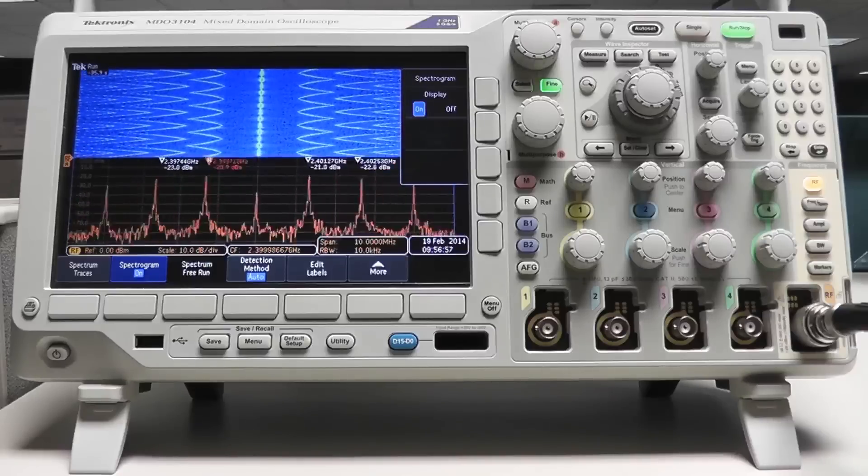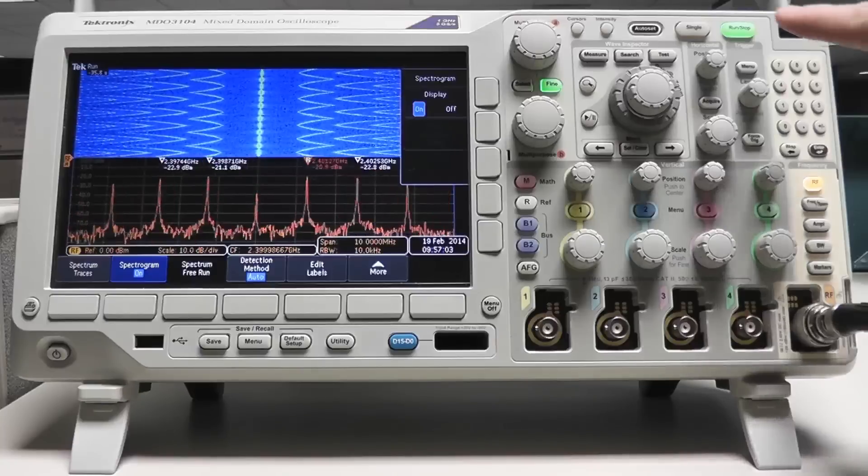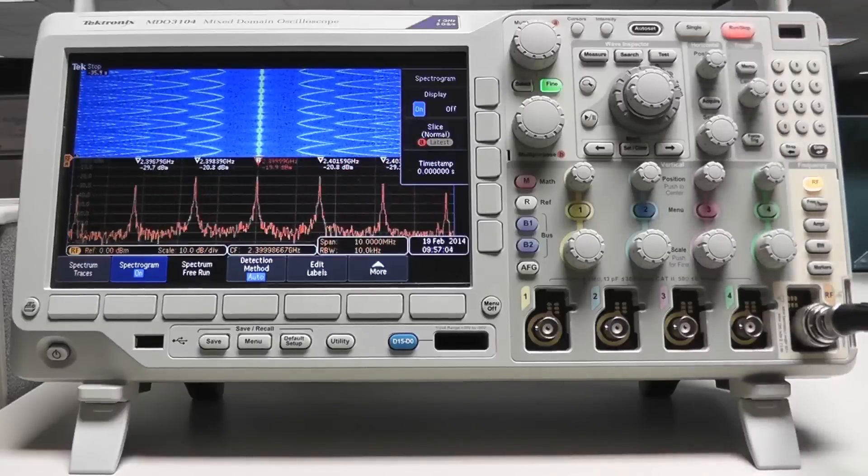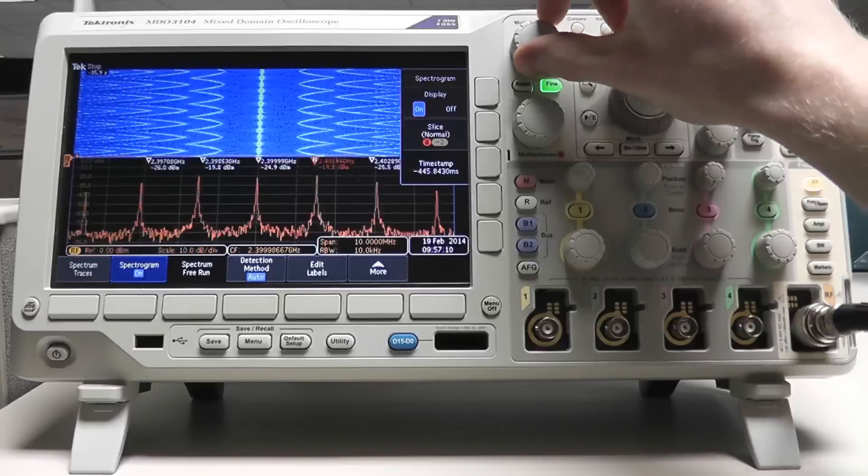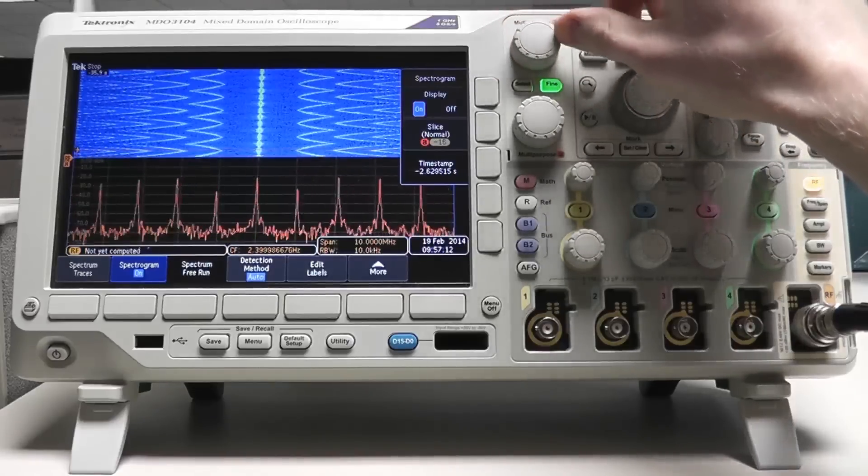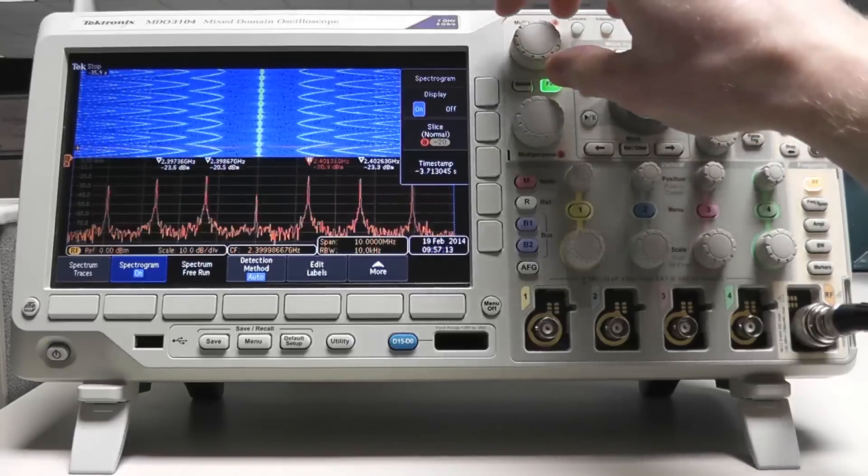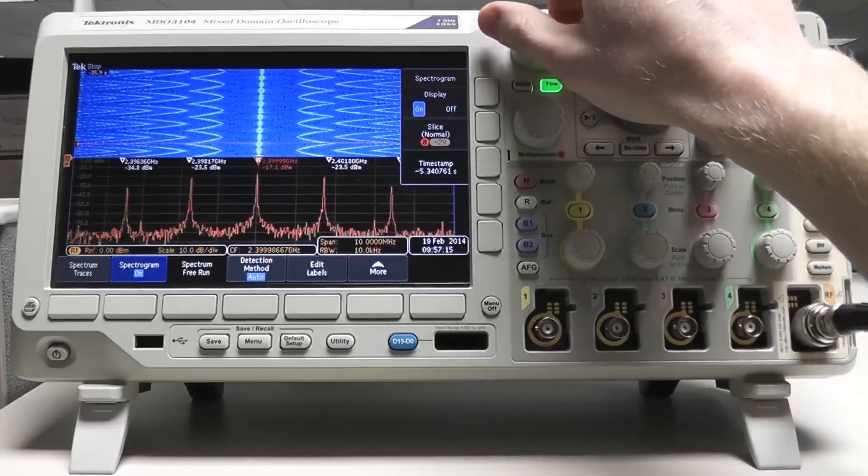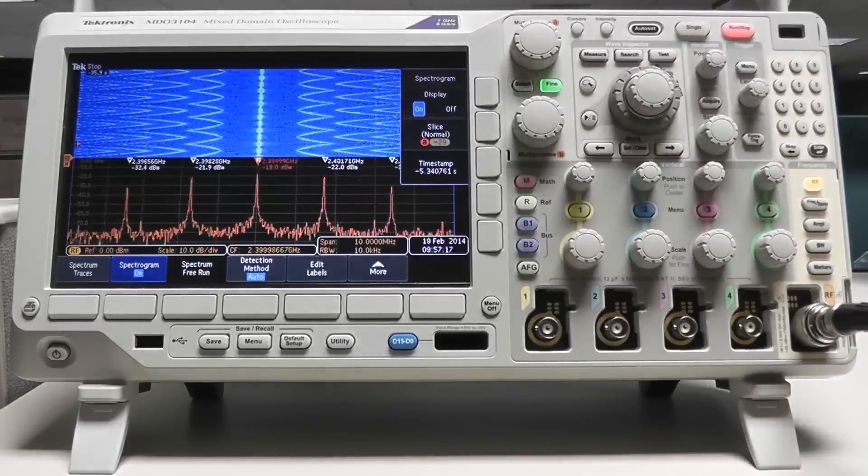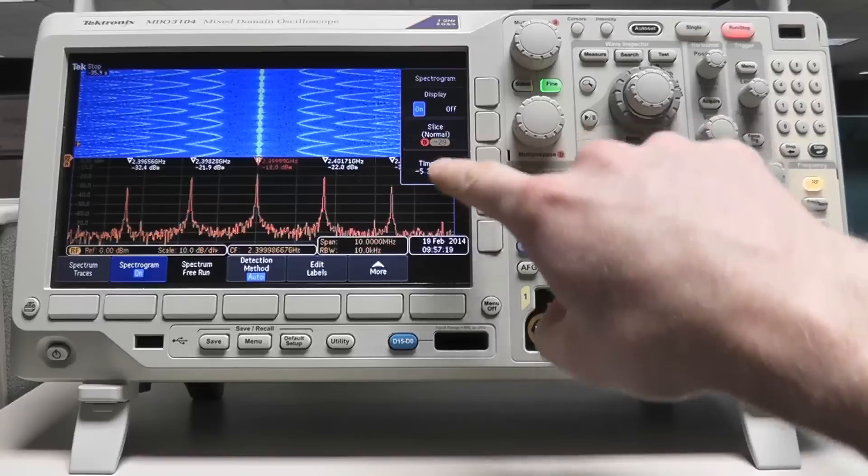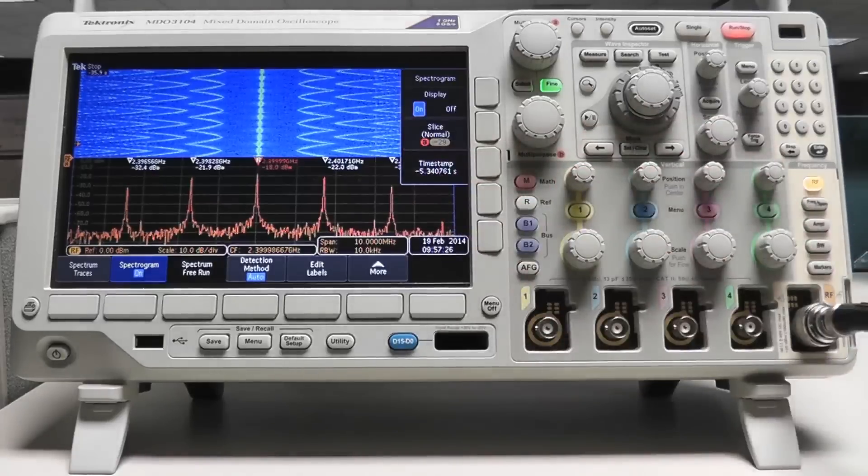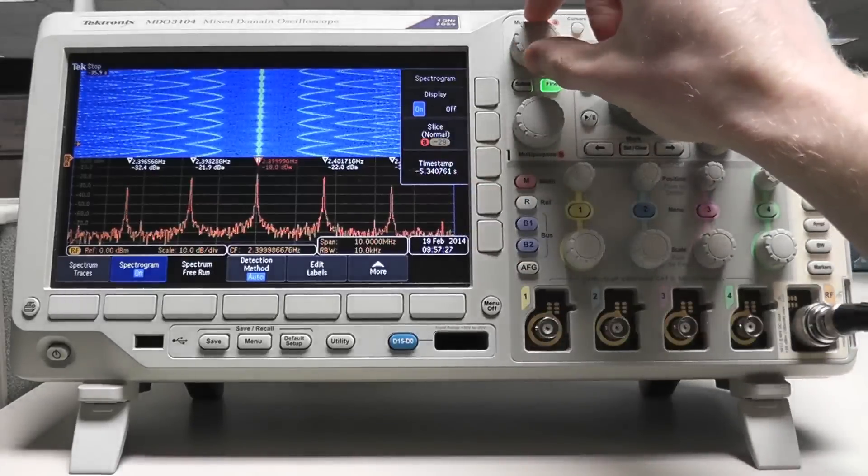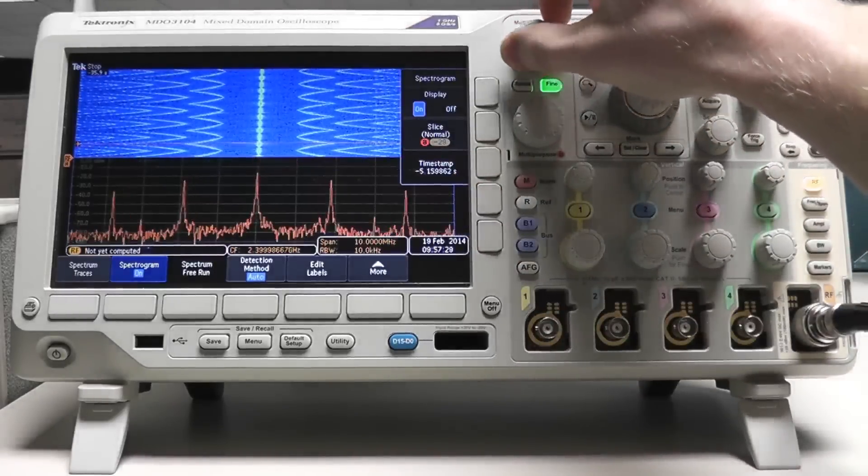When the spectrum analyzer is stopped, you can scroll through each slice of the spectrogram using multi-purpose knob A. Each slice shows the spectrum as it was captured at that time. Each slice is both numbered and time correlated. Notice that as the spectrum changes, the automatic markers will update as well.